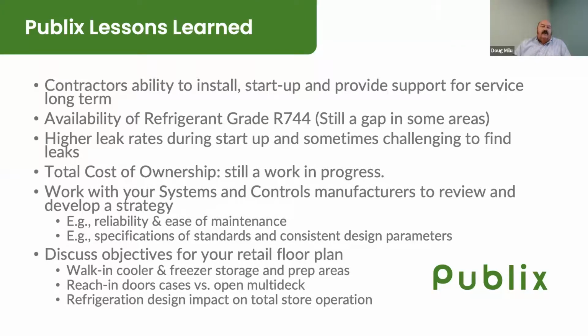Sure. Really early on, there was ambiguity with the contractors understanding the systems. But once we introduced the systems and worked alongside the contractors to get them installed and started, they realized it's just another refrigeration system. There are some components that are different, specifically working with CO2 - you handle it differently than HFC refrigerants during startup. Once you get over the nuances of handling CO2 as a refrigerant, the rest starts to fall into place - going through installation, startup, and working with those contractors on long-term support.